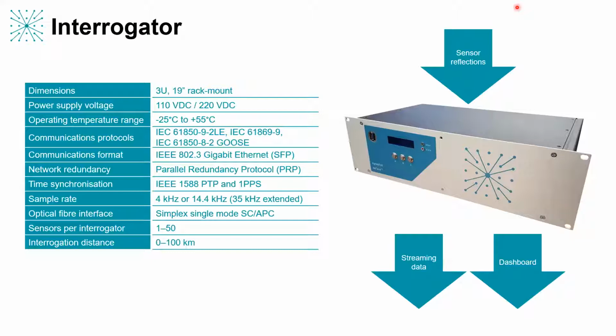The connection to the sensing fiber is dead easy. It's a single simplex SC APC plug connector. And from that one fiber, we can measure up to 50 sensing points spread over a distance of up to 100 kilometers.